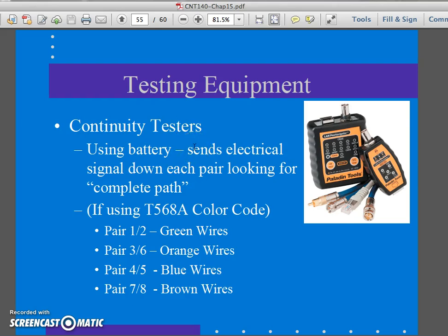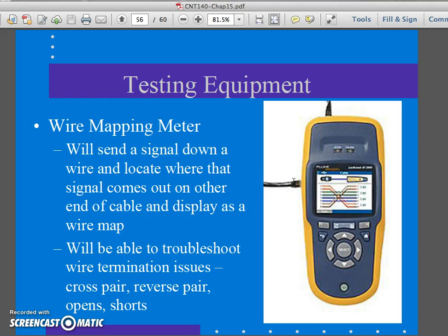Nothing about attenuation, near-end crosstalk. It's not capable of doing that. But that's your first test that is actually quite valuable, that can actually troubleshoot, that can find lots of your wiring problems for you right off the bat. It's very valuable in the process.